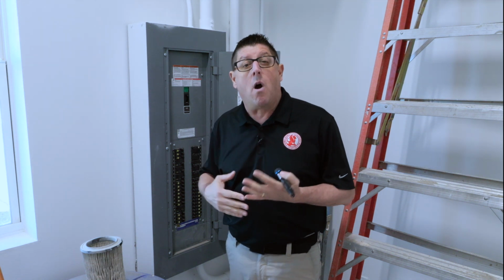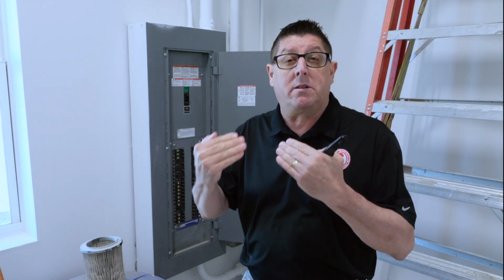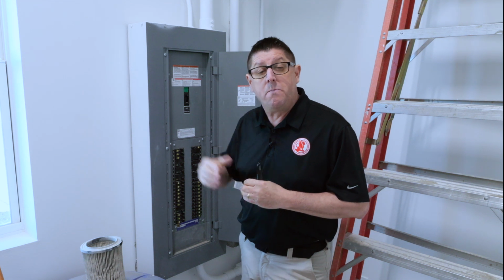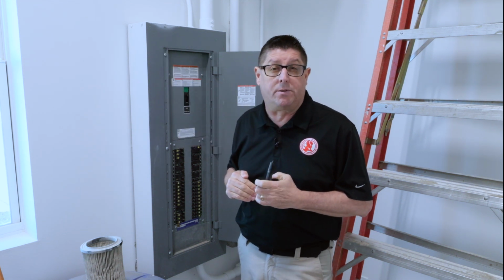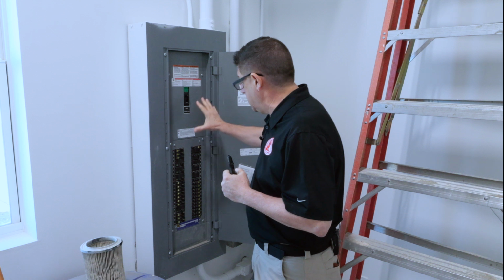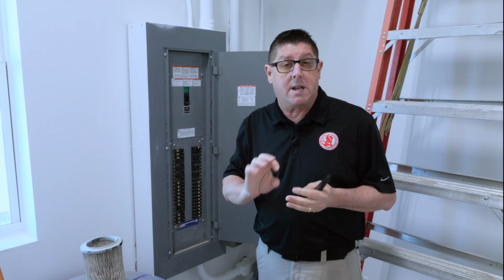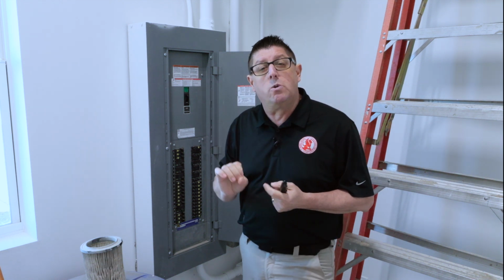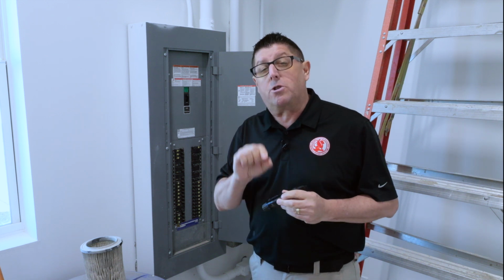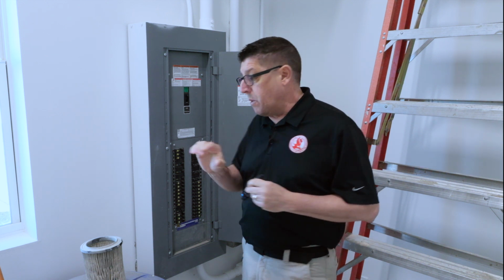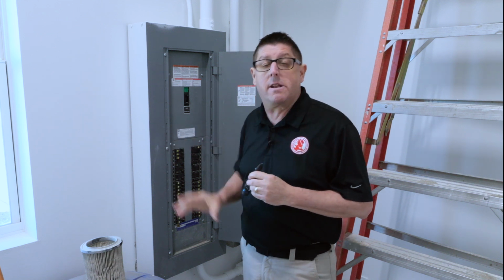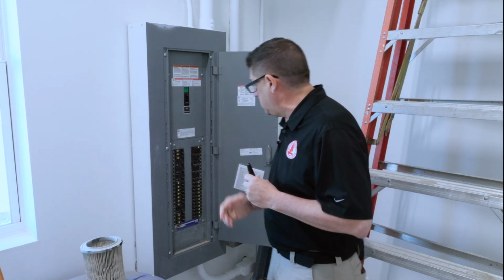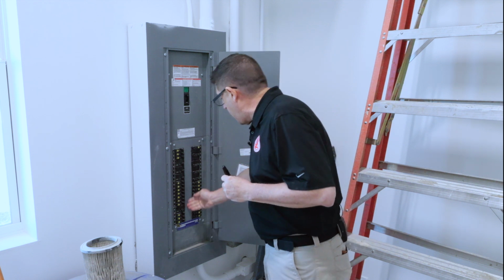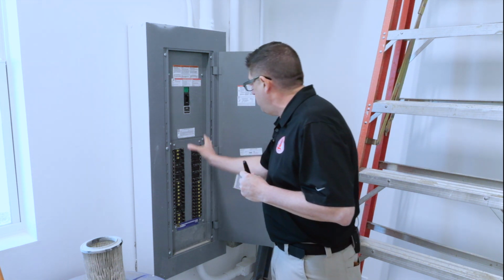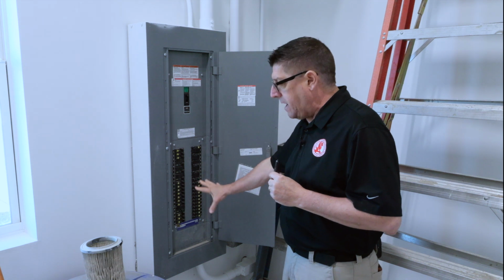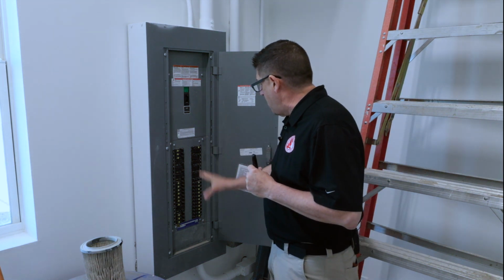So somehow, some way, we've stepped down our voltage from the high voltage of 600 volts to the 240 volts that this panel is. And so we need to identify the device used to step down that, which is called a transformer. And so when we're done with this panel, before I shut it, I will identify where our transformer is, but I'm going to finish the inside of this panel, looking at these breakers, making sure everybody's in place, I don't have any openings, and that I don't have any burn marks.